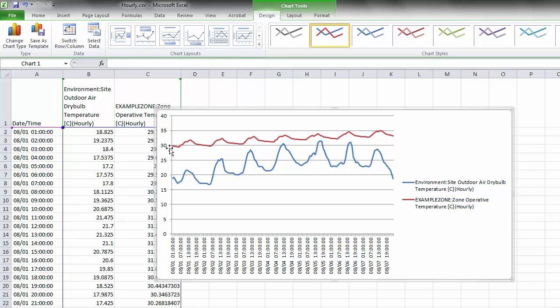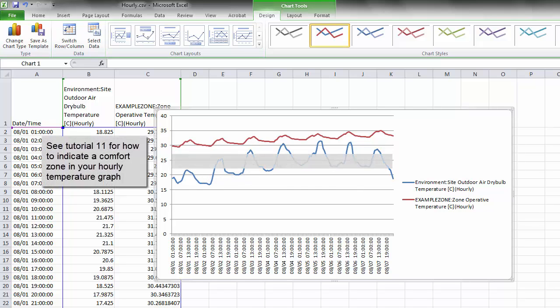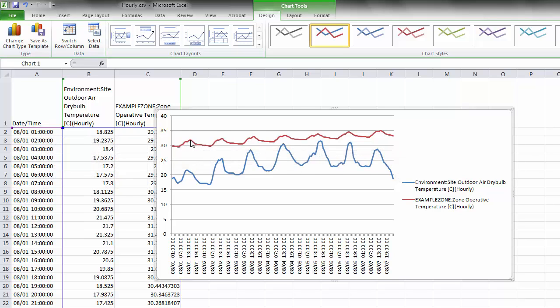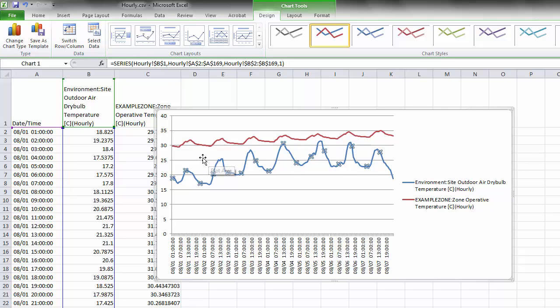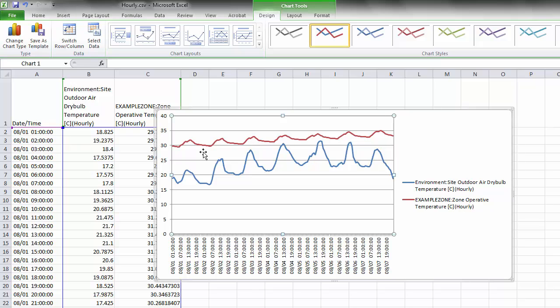We can see that the zone operative temperature is well above 30 degrees for most of this week, even though the outdoor temperature is dipping in and out of the comfort zone for most of the period. Because there aren't very many peaks and valleys in the indoor temperature compared to the outdoor temperature, we can see that our roof, floor, and wall assemblies — which have concrete on the interior — are providing thermal mass for heat storage. However, the temperature throughout the week is accumulating and we can see there is an overheating problem during this week.